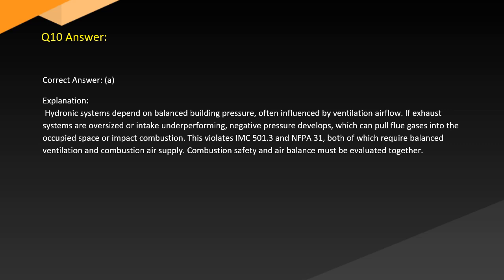Answer. Correct answer: A. Explanation. Hydronic systems depend on balanced building pressure, often influenced by ventilation airflow. If exhaust systems are oversized or intake underperforming, negative pressure develops, which can pull flue gases into the occupied space or impact combustion. This violates IMC 501.3 and NFPA 31, both of which require balanced ventilation and combustion air supply. Combustion safety and balance must be evaluated together.